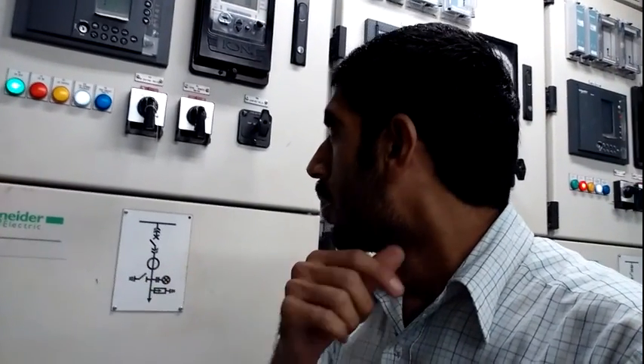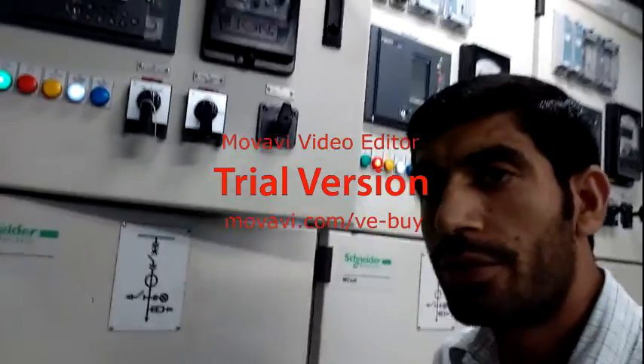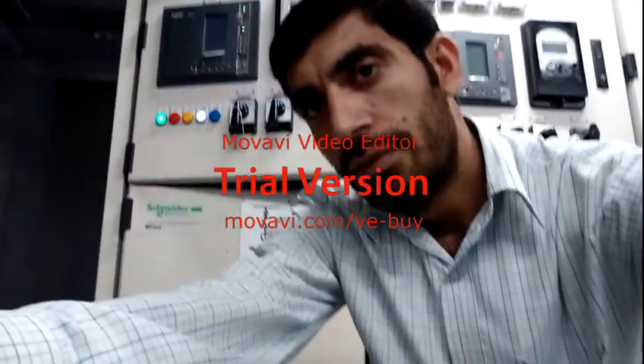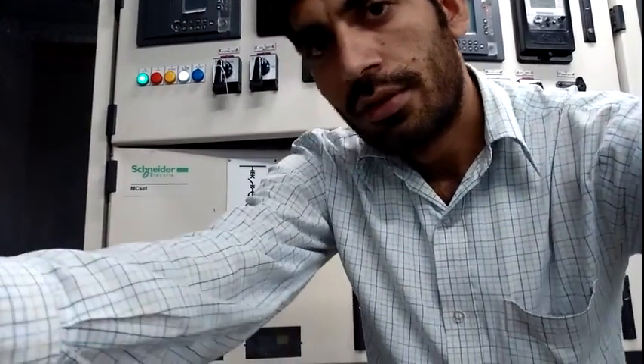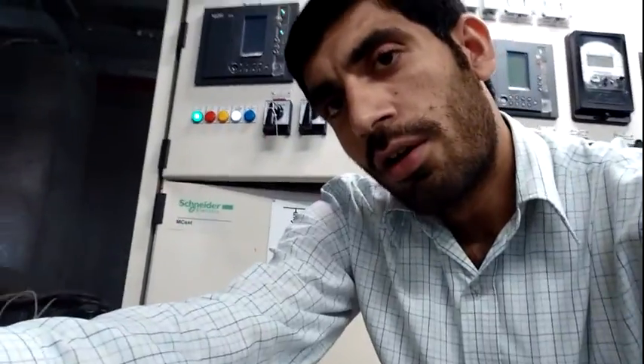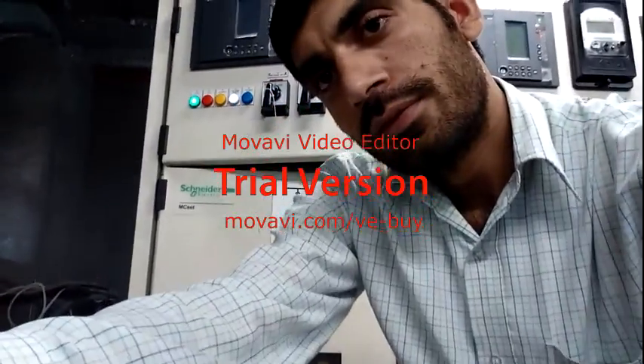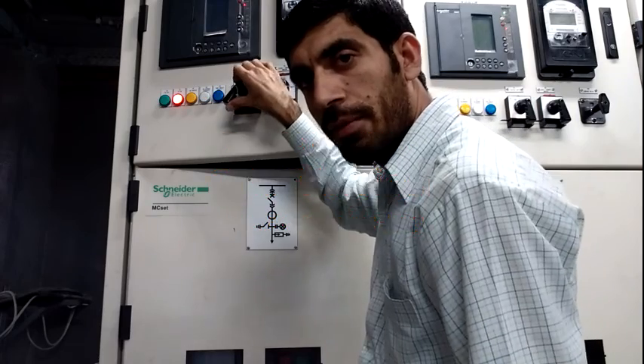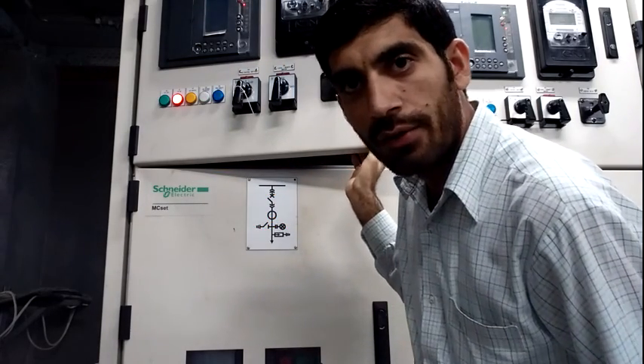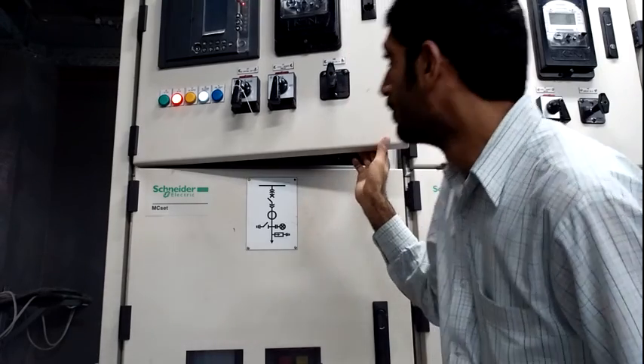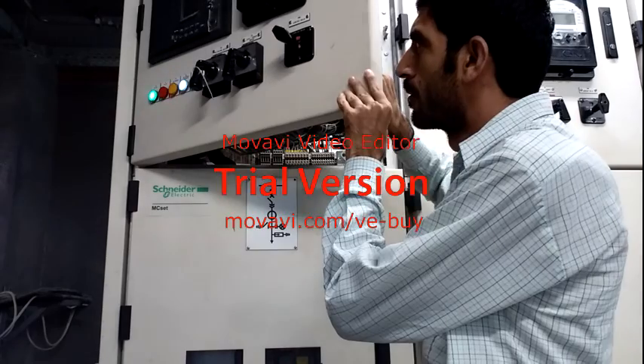Now I will show you how to operate this lockout relay. The actual situation is my breaker is open. Because my switch is in open condition, I can close the breaker. When I try to close it, the breaker is closed. Now I will operate the lockout relay, and this breaker will open. See, now my breaker is open and the lockout is operated.